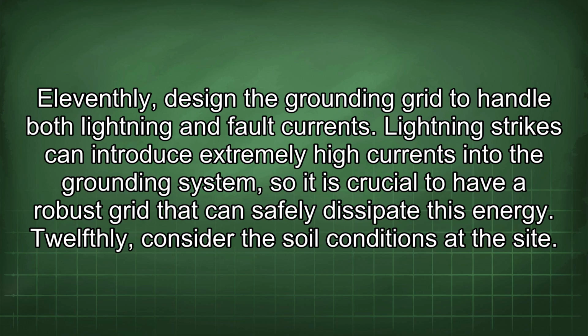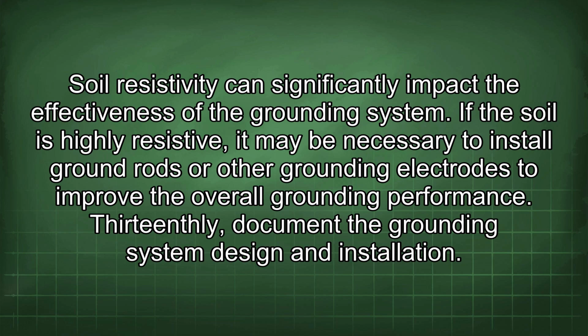Eleventhly, design the grounding grid to handle both lightning and fault currents. Lightning strikes can introduce extremely high currents into the grounding system, so it is crucial to have a robust grid that can safely dissipate this energy. Twelfthly, consider the soil conditions at the site. Soil resistivity can significantly impact the effectiveness of the grounding system. If the soil is highly resistive, it may be necessary to install ground rods or other grounding electrodes to improve the overall grounding performance.